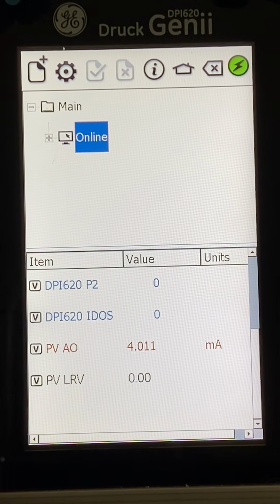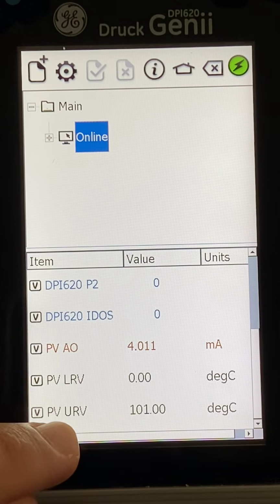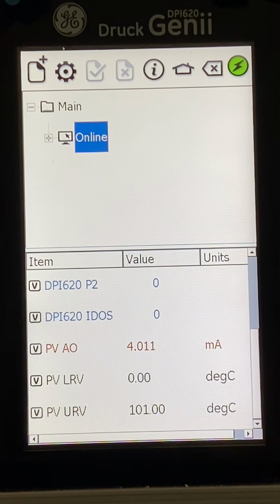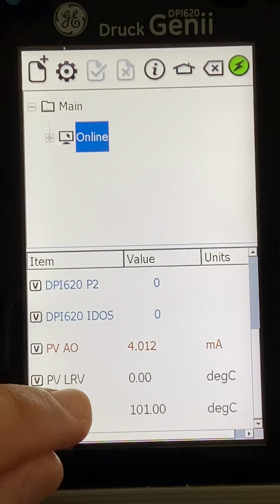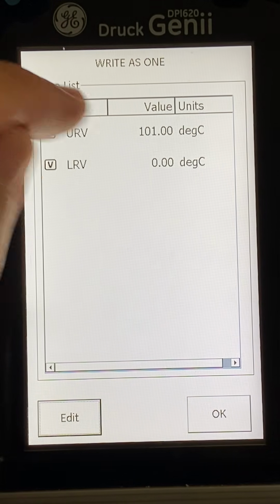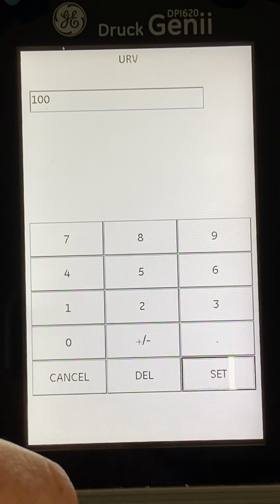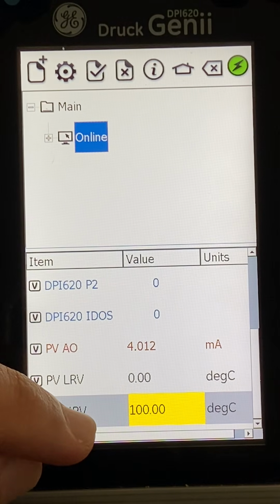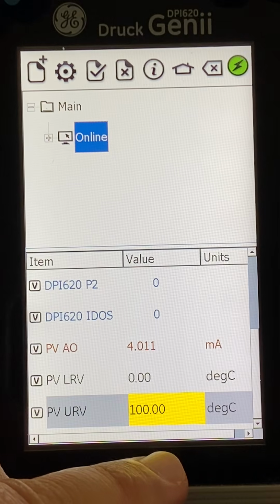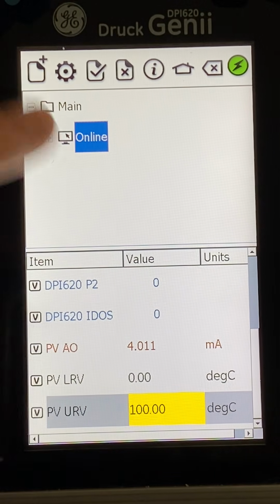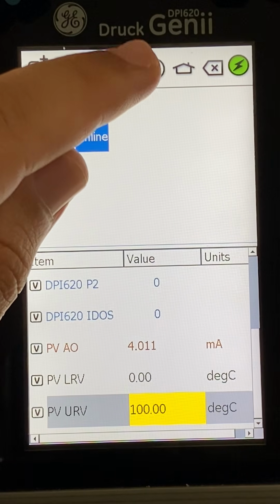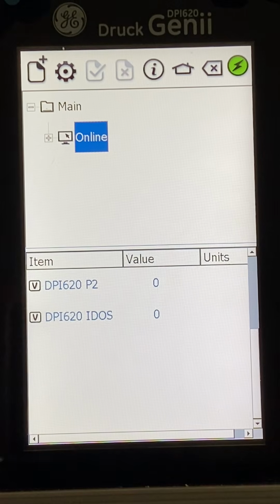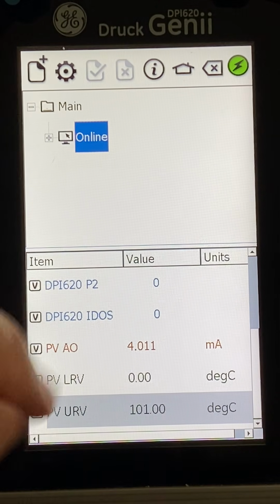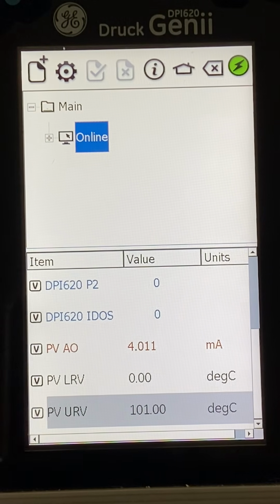In our case, the range we supposed was 0 to 100, but we see that the range, the URV, the upper range, is 101 degrees Celsius. This might be the cause of having the error at full scale. So simply, if I need to change it, just press on that. I can change it to 100. Okay. So the value now is not changing on the transmitter because it's still in yellow. Still in yellow means that it is not applied yet, it's not sent or transmitted to the device. So if I made any mistake, I simply can press on the cross and it will cancel all the modifications without saving them. If I press on the tick here, after doing any modification, it will be applied immediately. So this is one option for how we change the range.